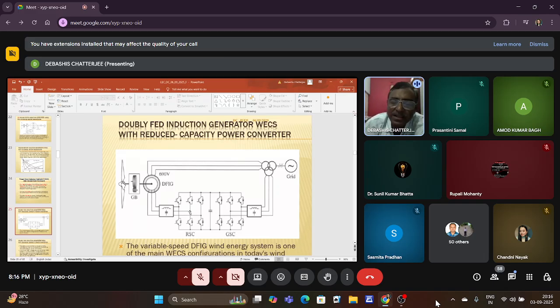This is the rotor side converter and the grid side converter. The rotor side converter is effectively, virtually changing the rotor resistances. Virtually changing means it does not produce any additional rotor loss, right? Because it is a virtual resistance. And then this is the grid side converter, which converts this DC voltage to the grid. Now this is known as DFIG, doubly fed, meaning the stator is also feeding and the rotor is also fed, or the stator sometimes feeds power while the rotor extracts power. So the general term is doubly fed induction generator, and it was actually termed from the doubly fed induction motor, DFIM, and then it became DFIG. Now why? How does it help you?